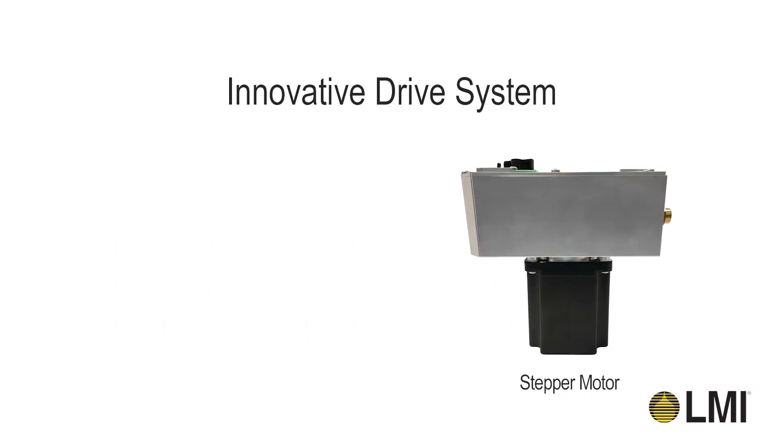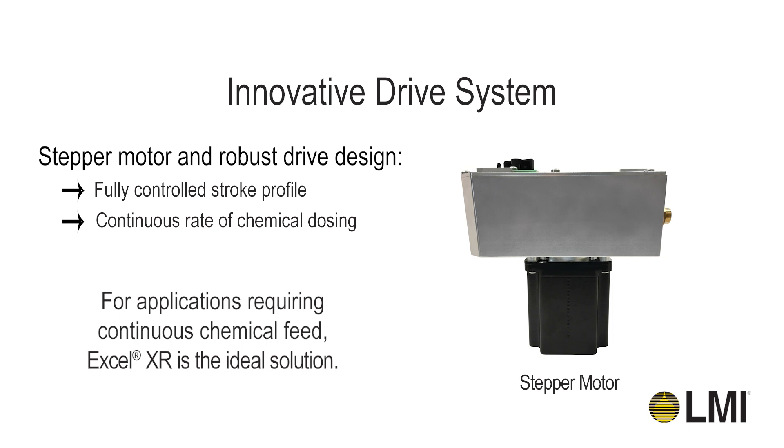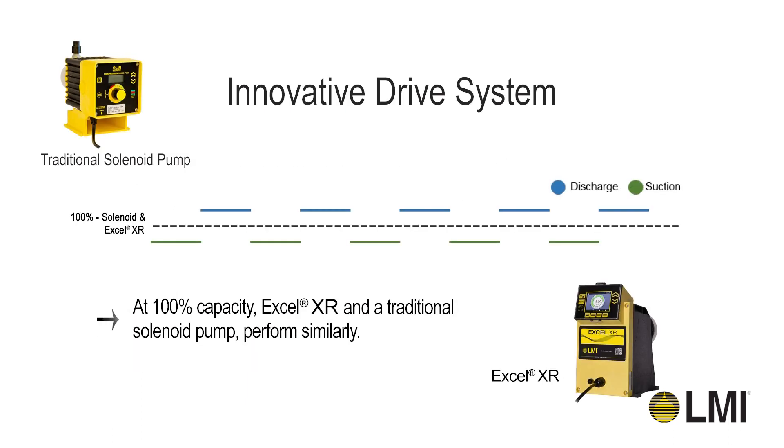Unlike traditional solenoid pumps, Excel XR Pumps are driven by a variable speed motor, allowing for a fully controlled stroke profile, which gives a continuous rate of chemical dosing. For applications requiring continuous chemical feed, the Excel XR Series is the ideal solution. At 100% capacity, there is little difference between the Excel XR Pump and traditional solenoid pumps, as the suction and discharge stroke profiles are very similar.